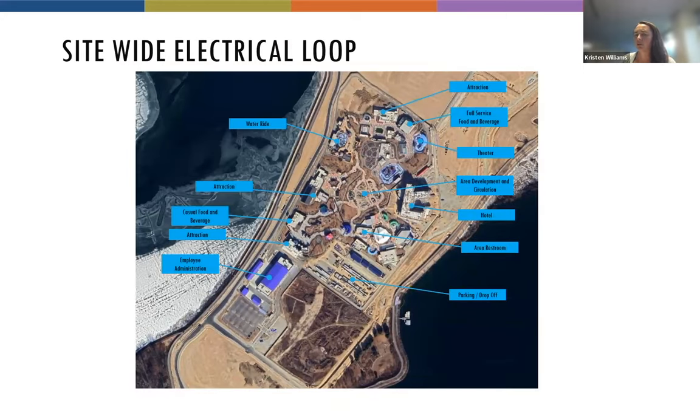These things take a lot of space, which is why planning at this stage is important. That red line is indicative of large conduits — maybe four-inch or larger, possibly concrete encased with a concrete cap. We're also planning for the switchgear that supports it: you may have a room of switchgear or a yard outside with switchgear located. And utility transformers — the green boxes everyone wants to hide — are generally fairly large and require about 10 feet of clearance in front of them. It's important when planning the site to know where these are going to be.